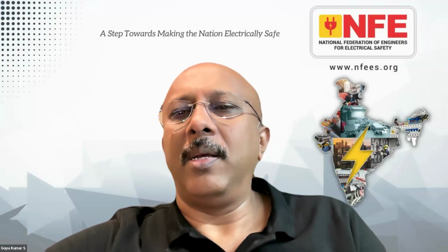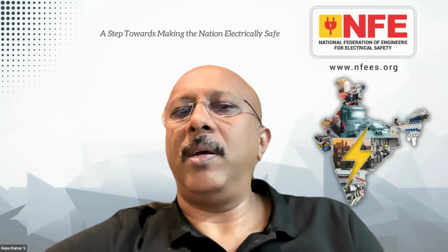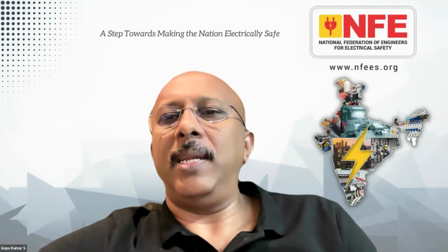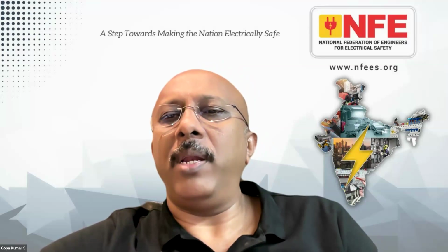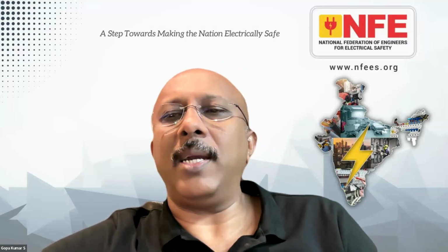Coming back to the next question. There is an anonymous attendee, probably to Krish. The question is, what are the advantages considering the reactance of a conductor? It's not a question of advantages or disadvantages. It's a question of you need to do it because every conductor that conducts alternating current has an impedance, and that impedance is broken down into a resistive and a reactive component. So there is no such advantage. You are required to take into account reactance as well as resistance for the calculation of impedance.